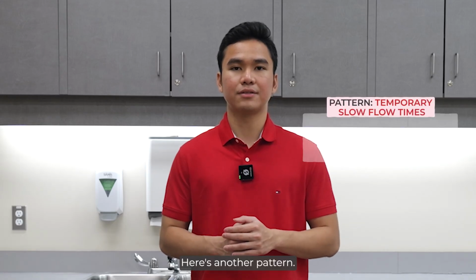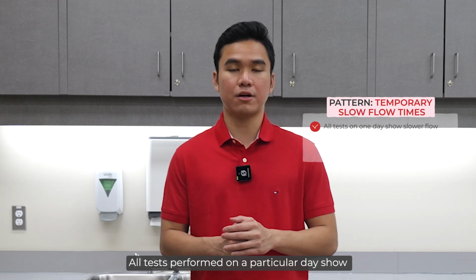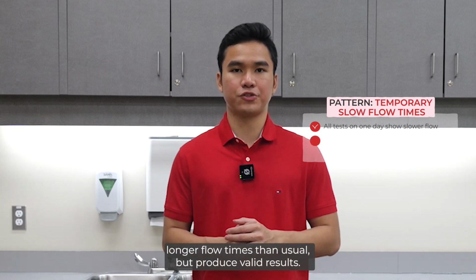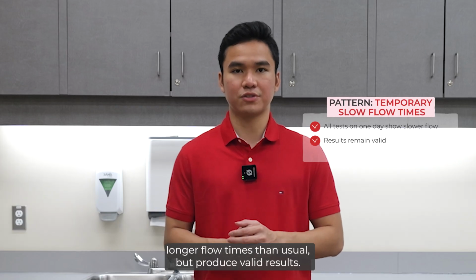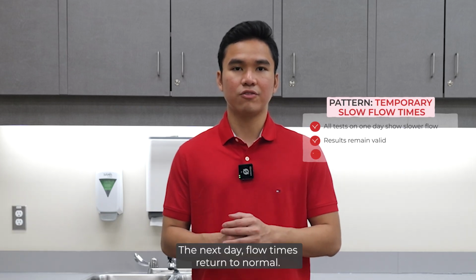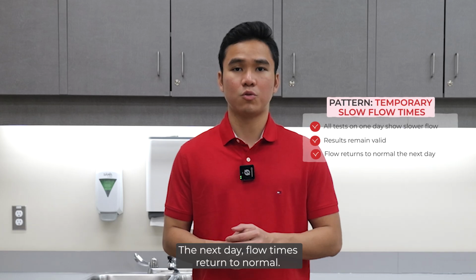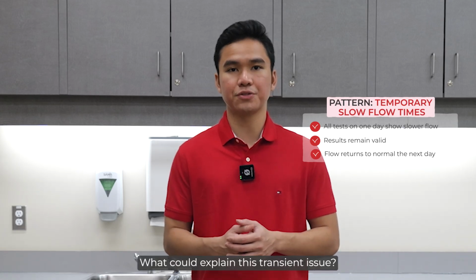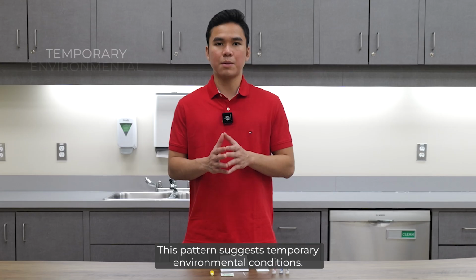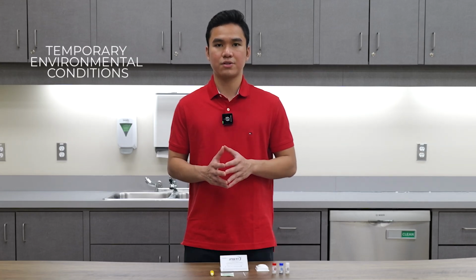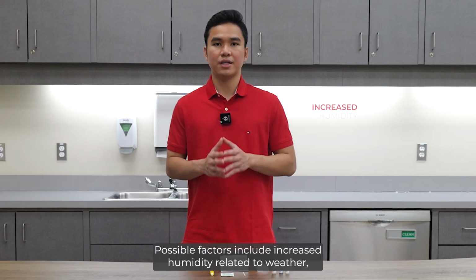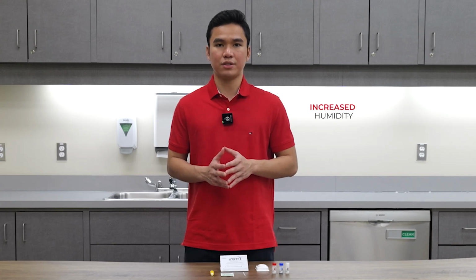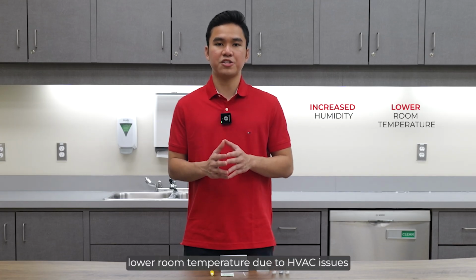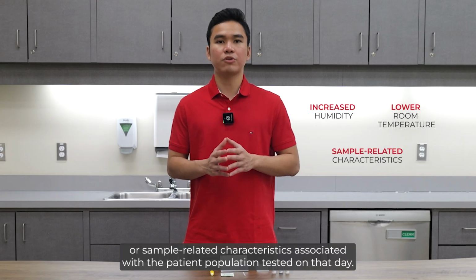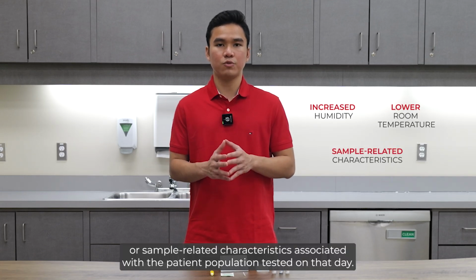Here's another pattern. All tests performed on a particular day show longer flow times than usual, but produce valid results. The next day, flow times return to normal. What could explain this transient issue? This pattern suggests temporary environmental conditions. Possible factors include increased humidity related to weather, lower room temperature due to HVAC issues, or sample-related characteristics associated with the patient population tested on that day.